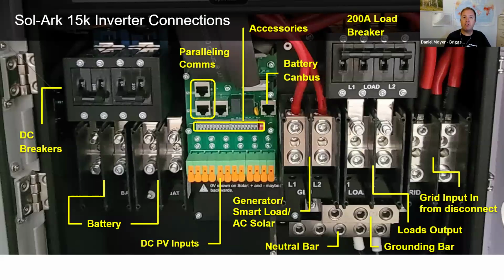As we move over to the center of our screen, we see the parallel comms. That's if you have multiple inverters. We have our battery CAN bus, which is where we plug in the batteries to the Sol-Ark so that the closed loop communications let the battery talk to the inverter, telling it its temperature and its health. Accessory pinouts, we're going to jump into that a little bit more here, but that's where you wire your rapid shutdown capabilities, the e-stop button, and the automatic generator start. Below that is where we land our solar. It's really nice to have those 3 MPPTs built in, and additionally to be able to parallel up strings, which may save you having to buy some Y connectors.